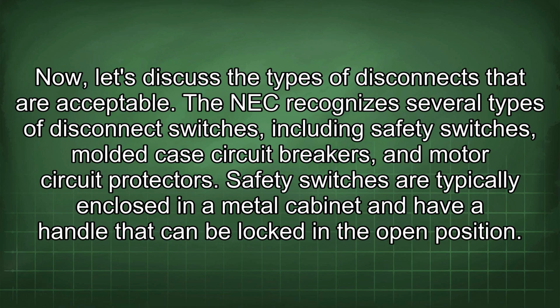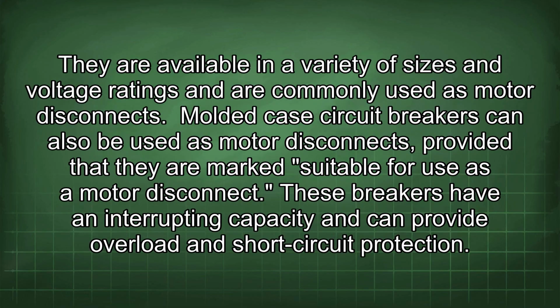Now let's discuss the types of disconnects that are acceptable. The NEC recognizes several types of disconnect switches, including safety switches, molded case circuit breakers, and motor circuit protectors. Safety switches are typically enclosed in a metal cabinet and have a handle that can be locked in the open position. They are available in a variety of sizes and voltage ratings and are commonly used as motor disconnects.